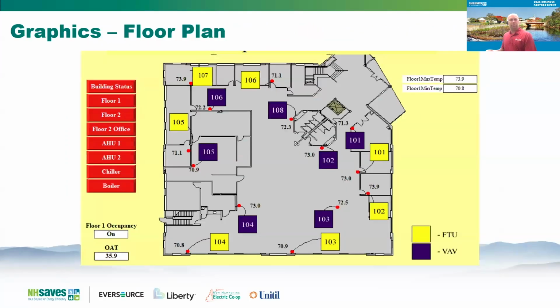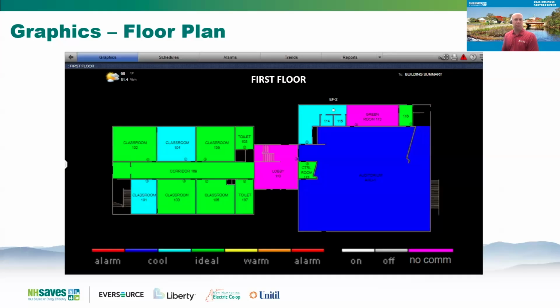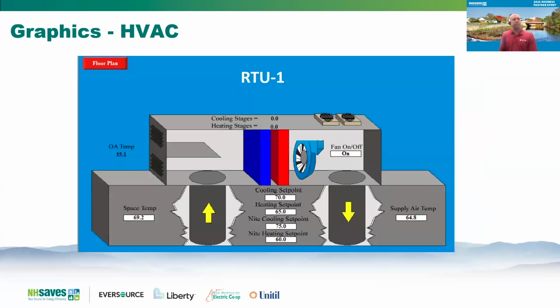So here's an example of a fairly antiquated control system's floor plans where they show the rooms, and you can click on each of the blue and yellow boxes and it'll bring you to a fan powered unit or a VAV box. But here's a more modern floor plan where they've got thermographics, which are color coded colors of each space to show you whether the room is satisfied or if it's in cooling or if it's in heating. It can provide a nice visual of where you're going to likely have hot or cold spots. Here's an example of an antiquated rooftop unit graphic. No animations, pretty choppy graphics. Still can work, just not as modernized.